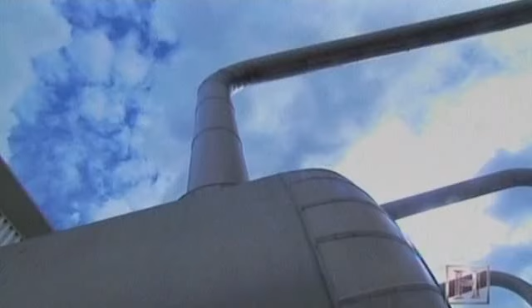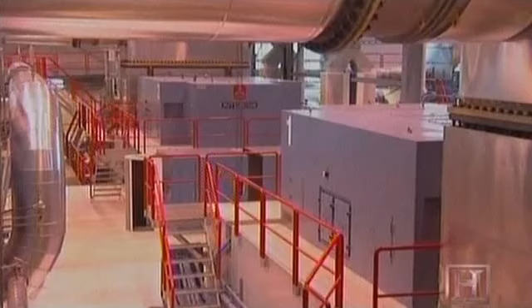A geothermal power plant for electricity works exactly like one using coal or oil in terms of the turbine, except this is natural steam. For electricity production, you're using the pressure of the steam, not the heat itself. The steam turns one of 4 turbines at a rate of 3,000 RPM. The turbines combine to generate 120 megawatts of electricity, which is sent on to Reykjavik.